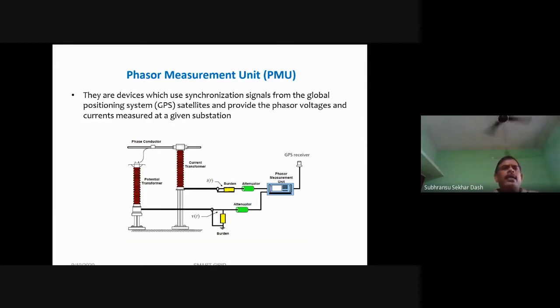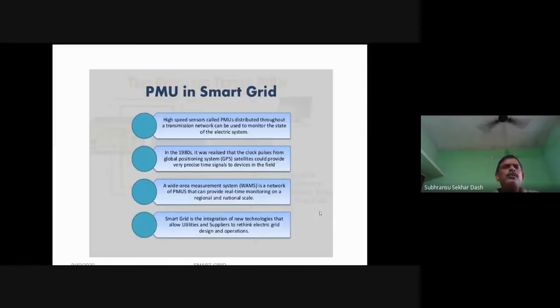They will get rectified output, and this is another output, which they will convert to digital for recording purposes. So PMU is the phasor measurement unit in the smart grid. The high speed sensors called PMUs, distributed throughout a transmission network, can be used to monitor the state of the electric system. In the 1980s, it was realized that the clock pulses from global positioning system satellites could provide a very precise time signal to devices in the field.